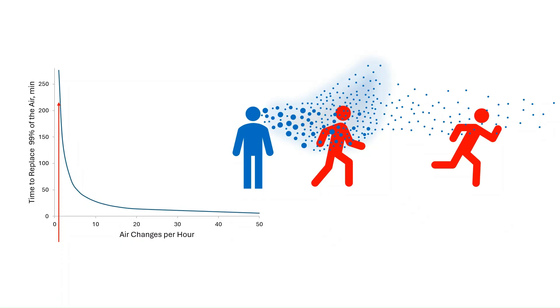For example, an ACH of 1 takes 276 minutes to replace 99% of the air. By increasing the ACH to 4, the time taken to replace 99% of the air drops to 69 minutes. This is a dramatic drop in time, demonstrating the importance of increasing the ventilation in poorly ventilated spaces.